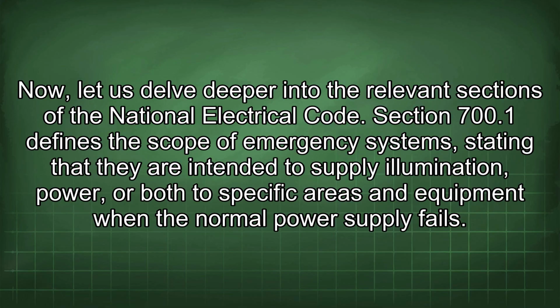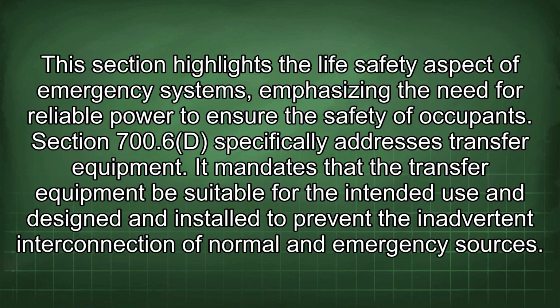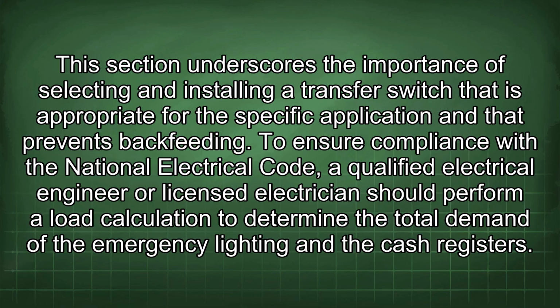Section 700.1 defines the scope of emergency systems, stating that they are intended to supply illumination, power, or both to specific areas and equipment when the normal power supply fails. This section highlights the life safety aspect of emergency systems, emphasizing the need for reliable power to ensure the safety of occupants. Section 700.6d specifically addresses transfer equipment. It mandates that the transfer equipment be suitable for the intended use and designed and installed to prevent the inadvertent interconnection of normal and emergency sources. This section underscores the importance of selecting and installing a transfer switch that is appropriate for the specific application and that prevents backfeeding.